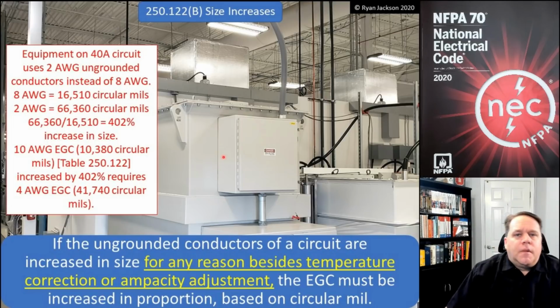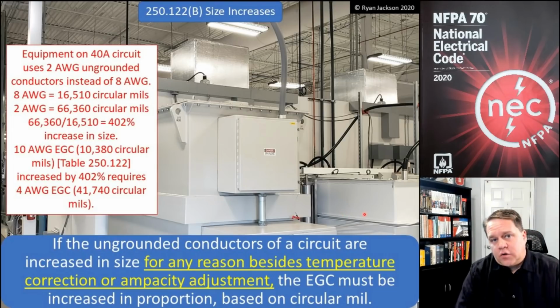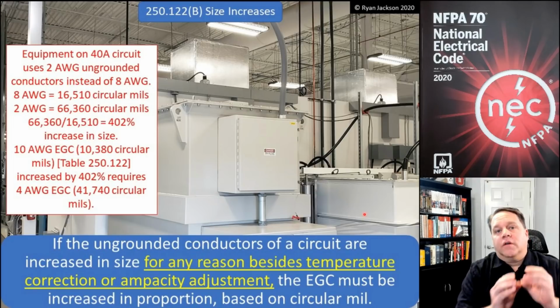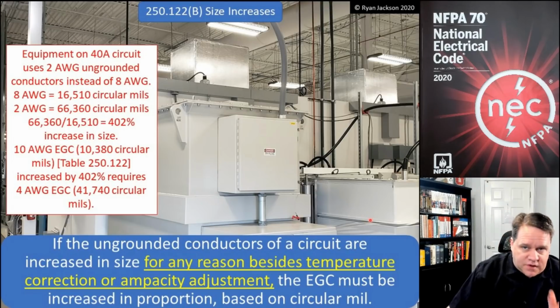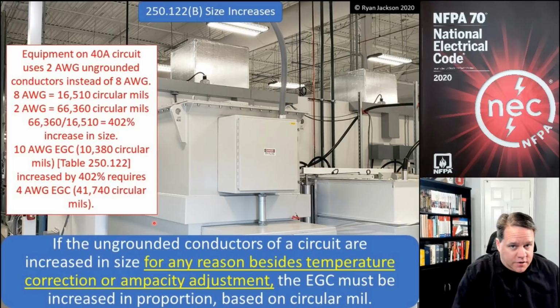Then I'm going to find my required equipment grounding conductor. This is a 40 amp circuit, which means at a minimum I would use a 10 gauge equipment ground. But because I increased the size of the ungrounded conductors, I now have to increase the size of the equipment grounding conductor in proportion. So I'm going to find the circular mil of my 10 gauge, same table, 10,380. I'm going to increase that by 402%, and that's going to result in a required circular mil area of 41,740 for my equipment grounding conductor.